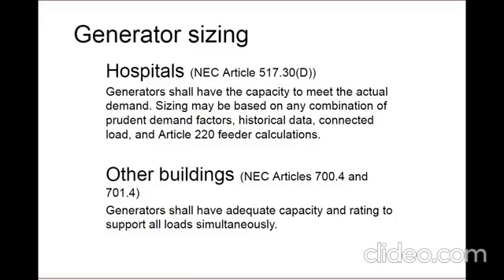NEC 517 permits practical sizing of the generator capacity using prudent demand factors and historical data, in addition to the connected loads and Article 220 calculations. Since the essential electrical system can often have a multitude of non-coincidental loads, it is not unheard of to see an actual demand on the generator of less than 30% of the connected loads. When a diesel generator is operating below 30% capacity, the engine cylinders and exhaust system may experience wet stacking. This is caused by an incomplete fuel burn and over an extended period of time can seriously degrade engine performance. Allowing a designer to size the generator closer to the expected peak demand gives good measure that the generator system will operate correctly over time.